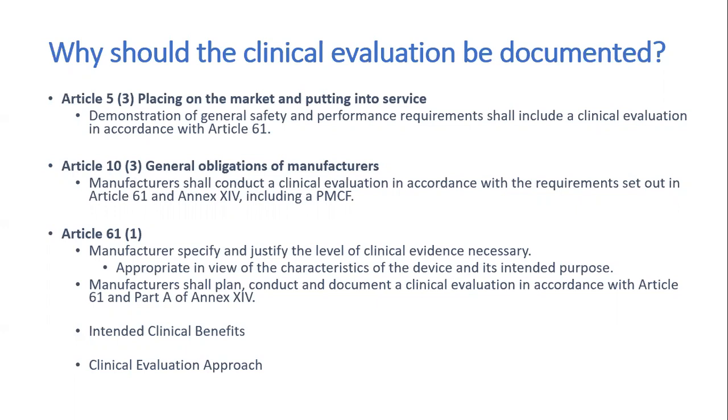The PMCF activities is post-market clinical follow-up. So for high-risk devices, PMCF is going to be taken, not for the low-risk devices. So for high-risk devices, when we put our product in the market, like class 2B and class 3, it is a must to have PMCF activity.